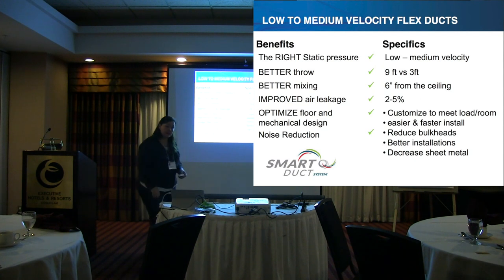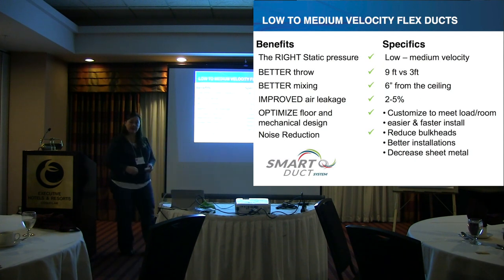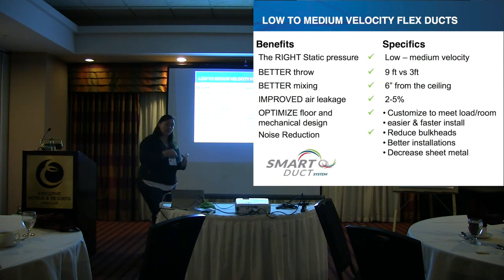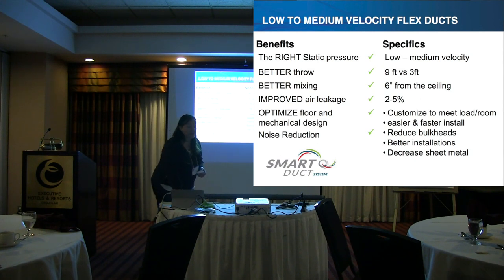So the fundamentals of the low to medium velocity system: the right static pressure mixed with that better throw, the 9 feet of throw with that better mixing that we've seen, improve the air leakage. These things screw together with 2 to 5% leakage. So that's a lot of time saved on getting that system sealed. And then again, optimizing the floor designs and mechanical designs.